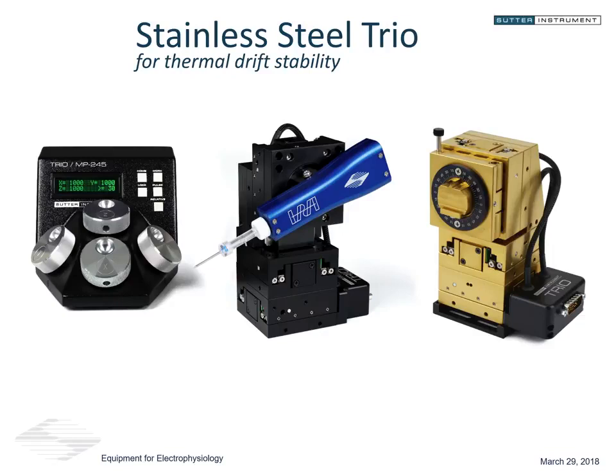I warn you, it also adds a considerable amount of weight. However, the thermal expansion coefficient of the stainless steel is about half that of the aluminum, so the stability that you get is noticeable. One of the other things that we found is that with the pretty intense weight of the stainless steel Trio, that tends to dampen some of the vibrations as well.